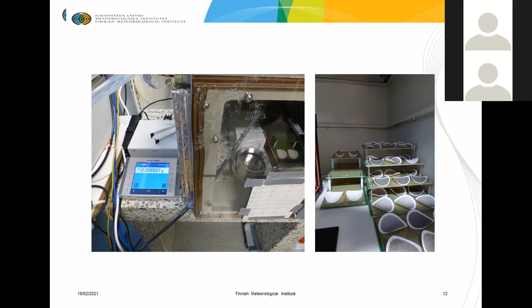Okay, of course, those were only the technical examples of the technical facilities that have to be in place to ensure the calibration and traceability for that. But of course, as I already mentioned, it's not only the measurement equipment itself, the characteristic of each instrumentation itself, that is defining the total accuracy of the measurements. It's also the calibration chain itself and the accuracy in that. And you have to remember that each step of the calibration and traceability chain has a different accuracy that is summing up at the end for the total uncertainty of the measurement.